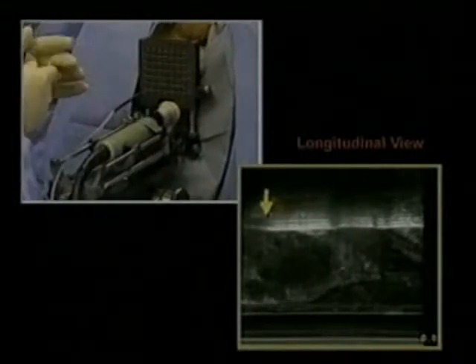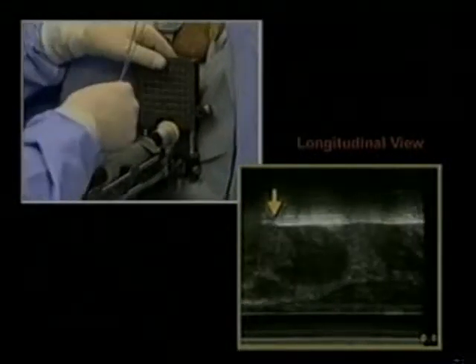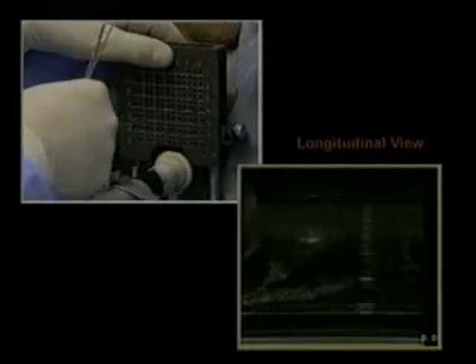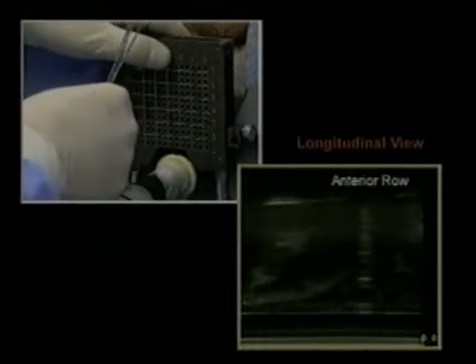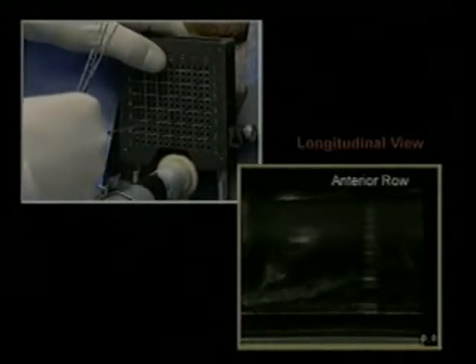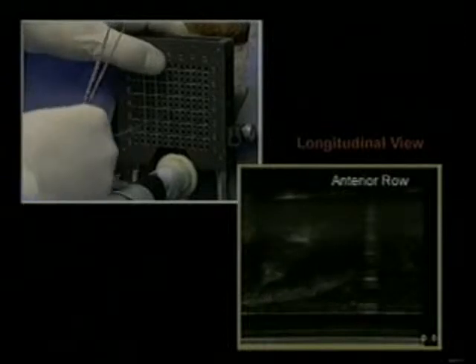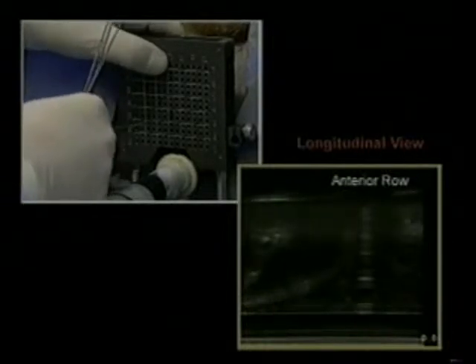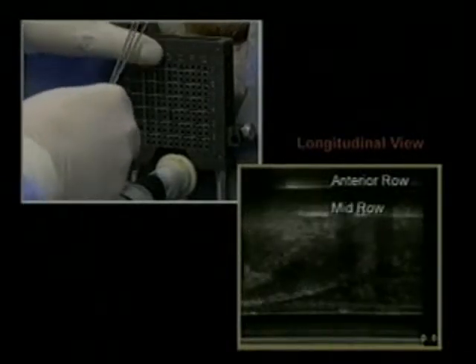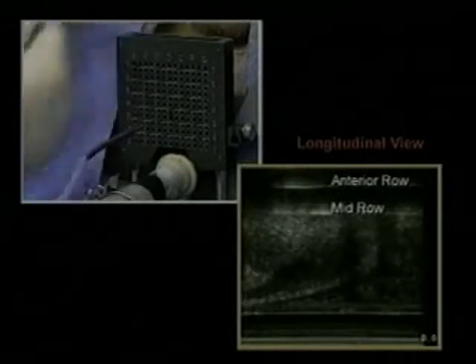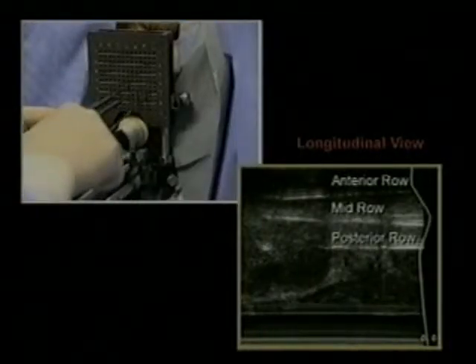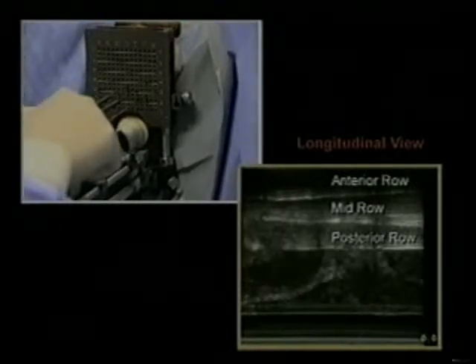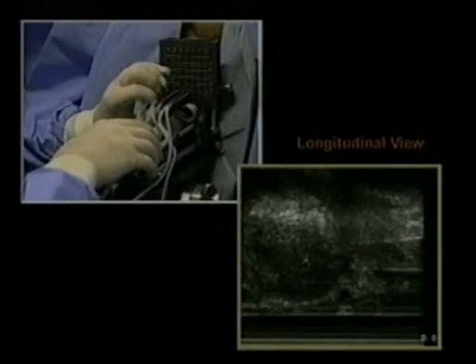The 17 gauge probes are directly inserted all the way to the base of the gland through the aiming template under constant ultrasound monitoring without the need for an insertion kit or dilation. A total of 12 to 15 probes in 3 to 4 rows are inserted into the gland to assure full coverage of the entire prostate. Each row is controlled as a separate unit by the computerized cryosurgical system.